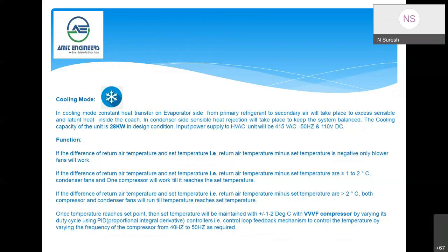The set temperature will be maintained within plus or minus 1 to 2 degrees Celsius with the VVVF compressor by varying its duty cycle using PID control, that is, proportional integral derivative control. That is a control loop feedback mechanism to control the temperature by varying the frequency of the compressor from 40 to 50 Hz. It may even go below 40 if required, that's not an issue.